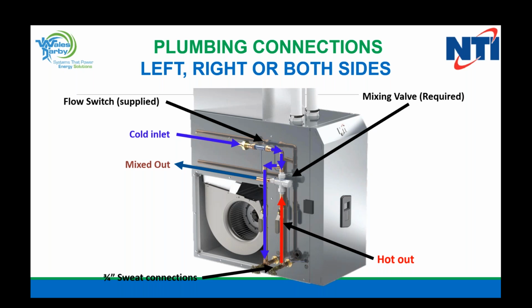So there's a door switch on these. Some guys will remove the door and then they'll put the return air right up against the side of the furnace. But there's a door switch on the right and the left-hand side. So if you don't cut your return air grill in, you just remove the door. Now you have a door switch. It's not going to allow the unit to run. So I just want to point that out so everybody is aware of it. So you don't get it out to the job site and find out that it won't run after you do it. So be aware of that. The piping, again, right or left side. Right below the arrow, let me just show you one thing here, because this is something you have to install on the job.